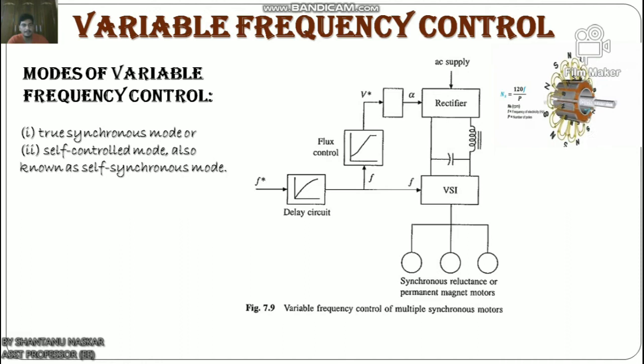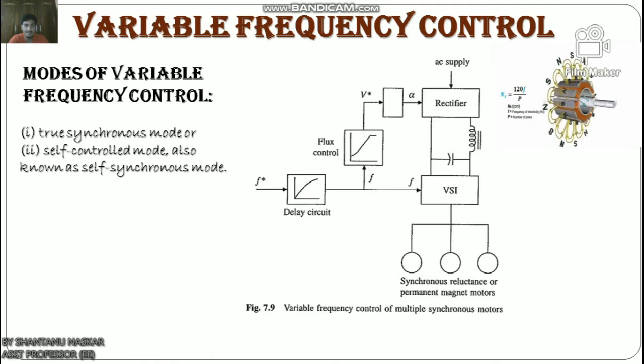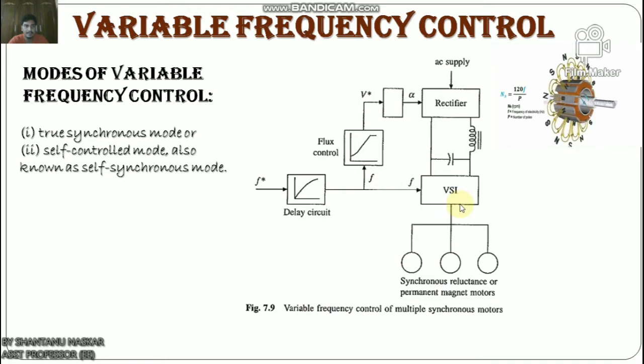For all types of synchronous motors, this gives operation with a constant pullout torque until rated voltage is reached at base speed. For higher speeds, the machine is operated at rated terminal voltage with variable frequency control, and the pullout torque decreases with an increase in frequency.